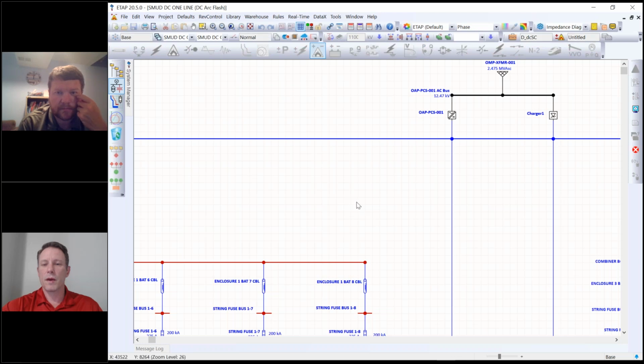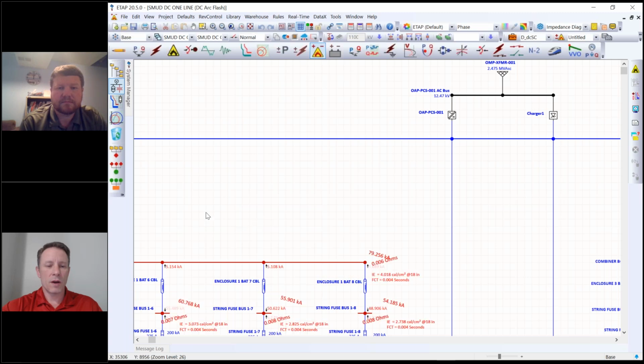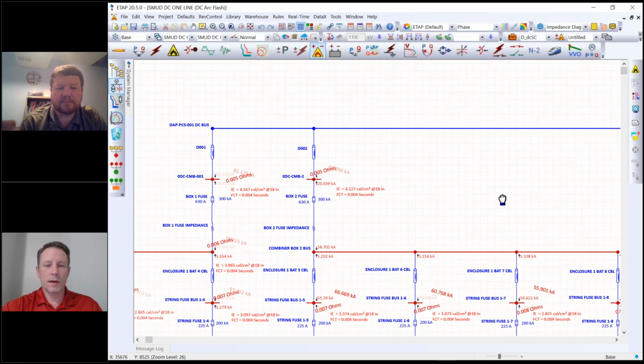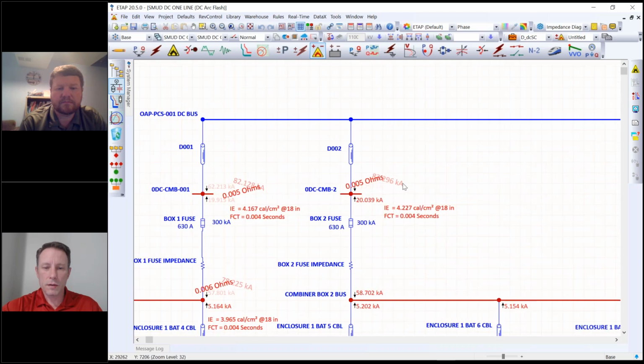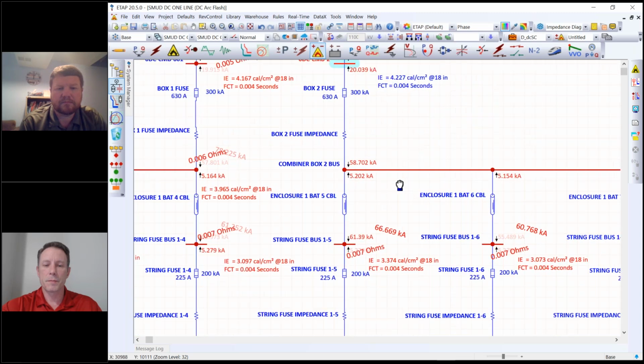So this is using ETAP to run the arc flash on the DC system. And we don't always use ETAP for this because sometimes it's hard to get exactly what you want out of it. It takes a minute to run. So at the inverter, I'm seeing about 4 cals right here because of those incredibly fast fuses. I think we actually got a little bit less when we calculated it with our spreadsheet, but it's still, 4 cals is not hard to live with.